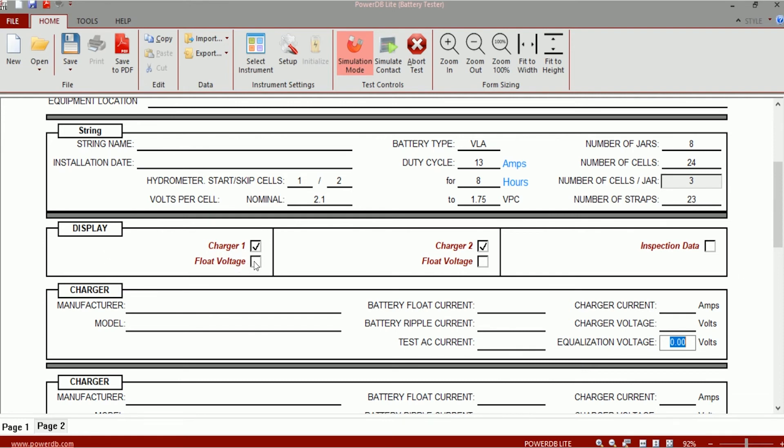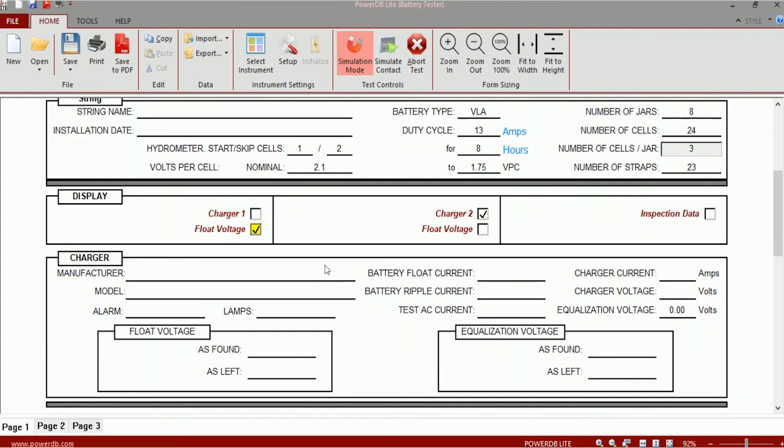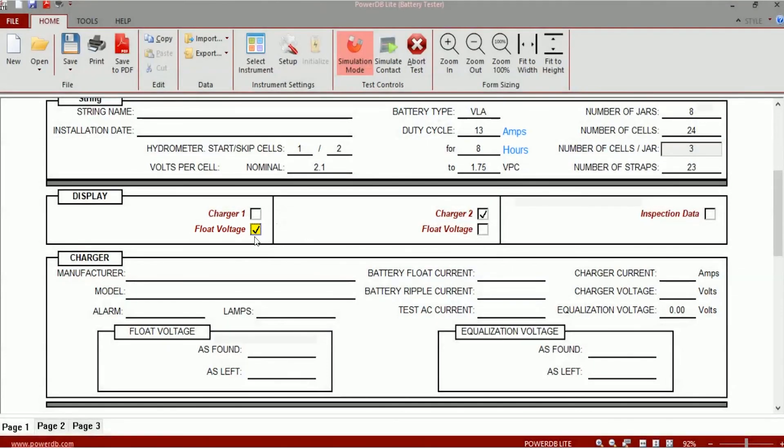If you want to enter as found and as left values for float voltage and equalization voltage, then you can certainly do that by checking on these boxes. Each one box is available for each charger.